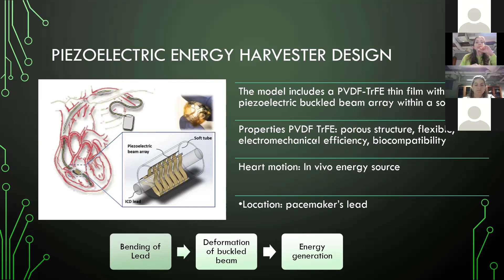Now, since the lead of the pacemaker follows the heart's motion, which is a complex motion throughout the cycle, the mechanical design has a complex motion, from which two movements are responsible for generating electrical current: the vibration of the piezoelectric beams and the bending moment generated from pressing the beam. As we can see in the graph, the voltage generated due to the vibration effect is very minimal when compared to the voltage generated due to the complex motion. So we can conclude that the bending motion of the piezoelectric buckled beam contributes most to the overall electrical output of the device.